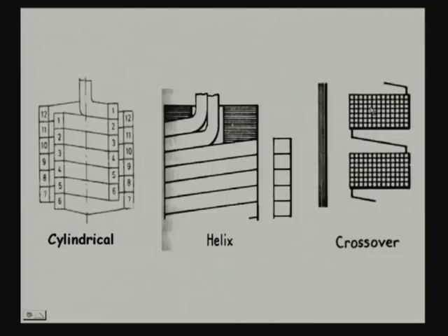For the high voltage winding, high voltage winding will usually have a large number of turns, but its current rating will be small. They can be still made up of rectangular wires or even circular wires. In the crossover winding, generally high voltage windings are divided into several groups and the groups are wound separately and then they are connected in series to form the high voltage winding. Each group can have many number of turns and they can be arranged in multiple layers.